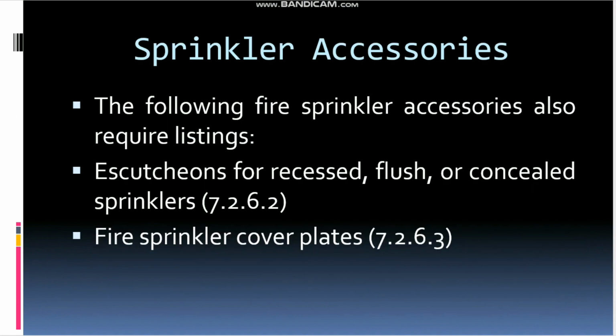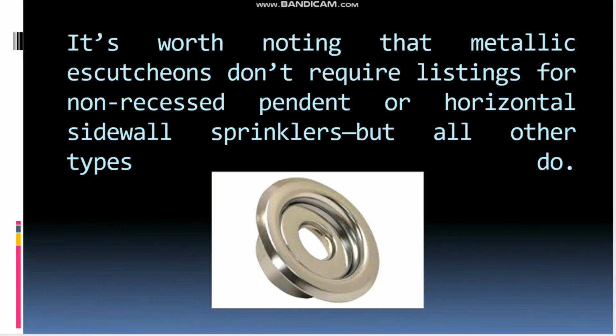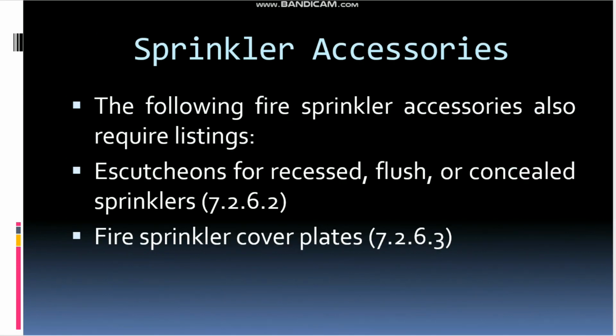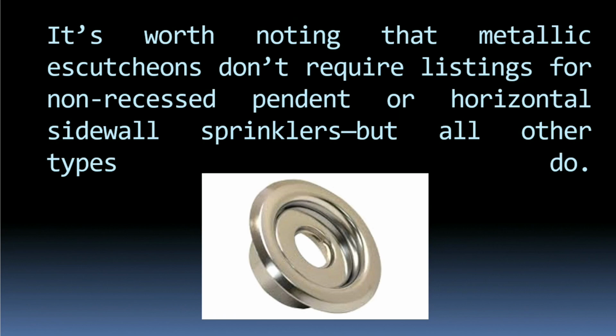As you know, sprinklers for the firefighting system must be listed because they affect the performance. But coming to the accessories, the following fire sprinkler accessories also require listing. Here is this important plate in the firefighting system: the escutcheon for recessed, flush or concealed sprinklers should be listed, and the fire sprinkler cover plate should be listed. The important point is that metallic escutcheons don't require listing for non-recessed pendant or horizontal sidewall sprinklers, but all other types do. So only for these two types of sprinklers we don't need the plate to be listed.